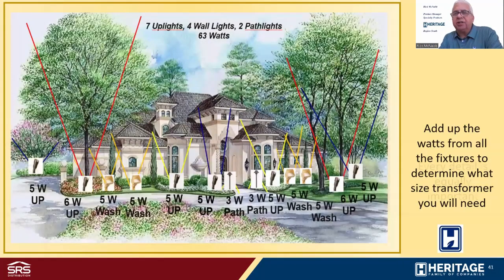So if we take a typical project like this, and we're looking at a front yard on this home, we specified 13 fixtures on this property to illuminate the front of the house. Some of the fixtures are 5 watt, some fixtures are 6 watt. I see the path lights here are 3 watt. So each of the fixtures may have a different wattage consumption. By adding all these up, we can come up with the total number of watts for this project. And so you can see here that on this particular job, we have a total of 63 watts.